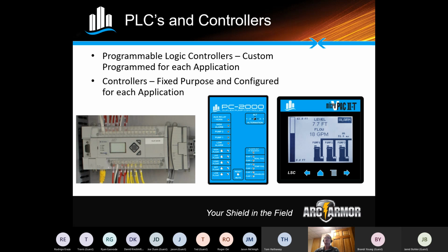All right, PLCs and controllers. Kind of what's the difference, or how do we distinguish between them, right? So a PLC is a programmable logic controller, custom programmed for so if I have a lift station, I need to control 2 pumps. I put an Allen Bradley, Schneider, GE, you name it, type controller PLC in there. Those are usually associated with a custom program that has to be downloaded in by somebody that can program. Whereas what we're calling controllers, they're normally a fixed purpose, or they can be configured. So they are application specific, and you basically pick and choose how you want those to operate.